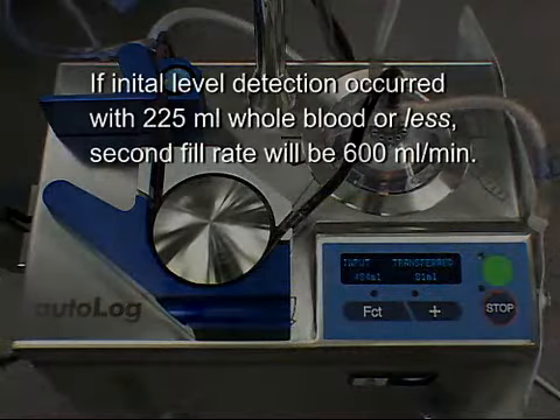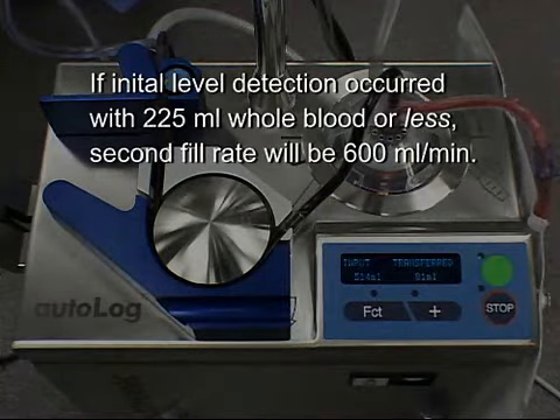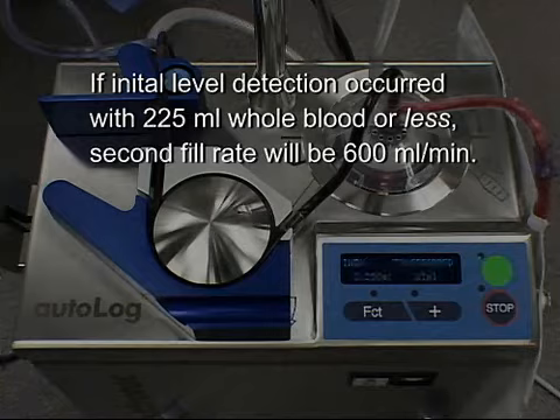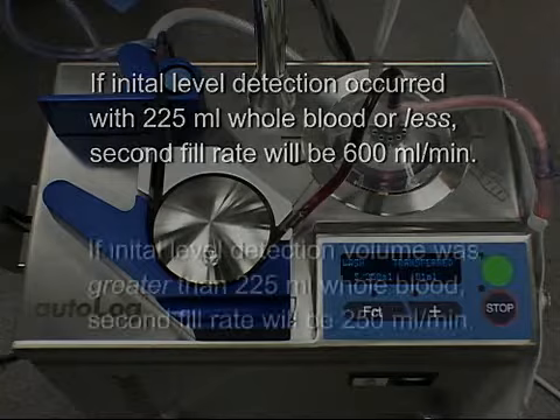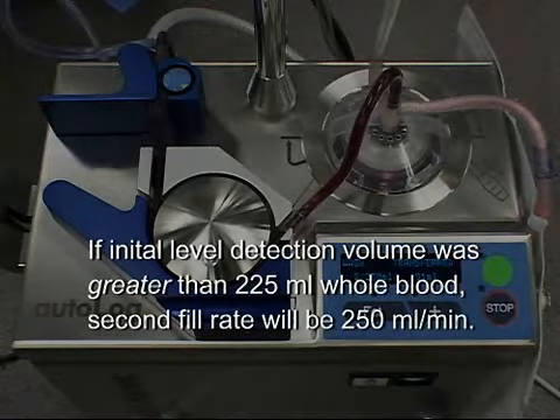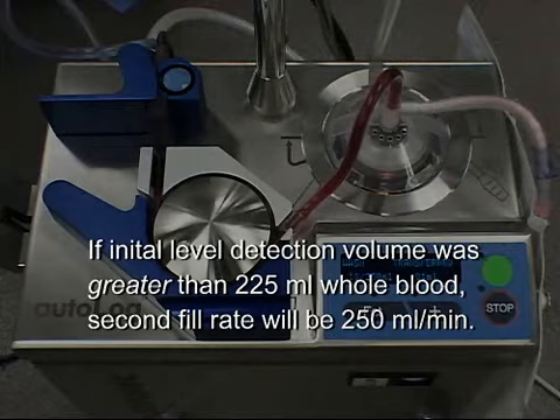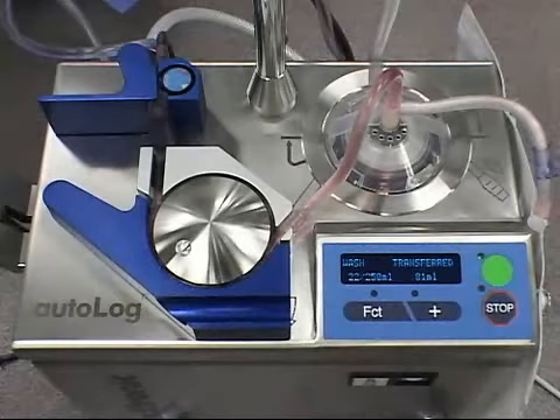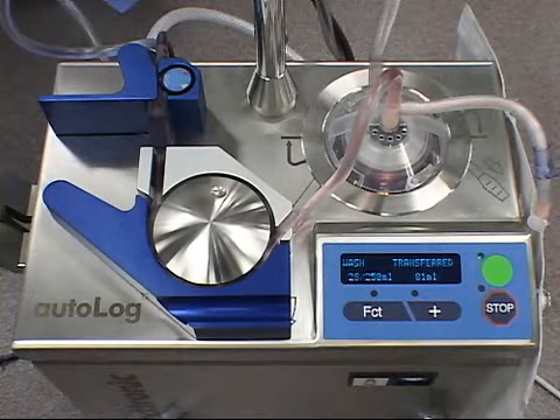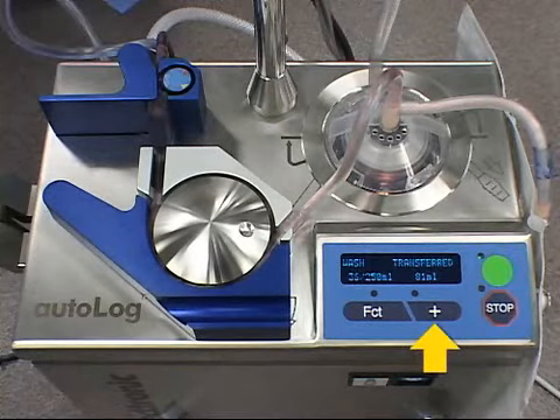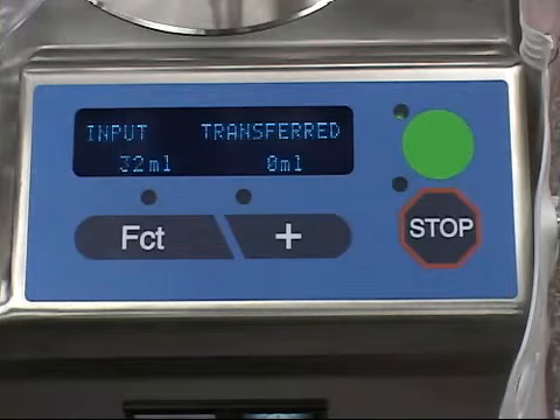If the initial level detection occurred with a volume of 225 milliliters of whole blood or less, the second fill rate will be 600 milliliters per minute. If the initial detection volume was greater than 225 milliliters of whole blood, then the second fill rate will be 250 milliliters per minute. The rate slowdown can also be triggered manually by pressing the incrementation plus key twice. In the fill cycle, the machine will display input 32 ml, transferred 0 ml.